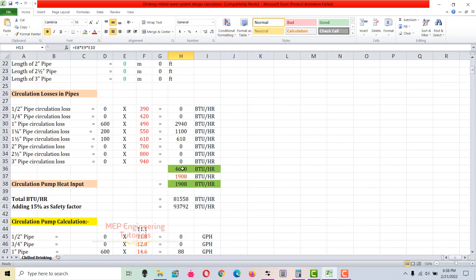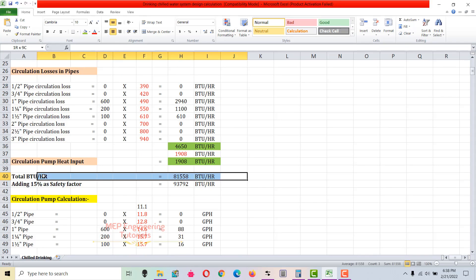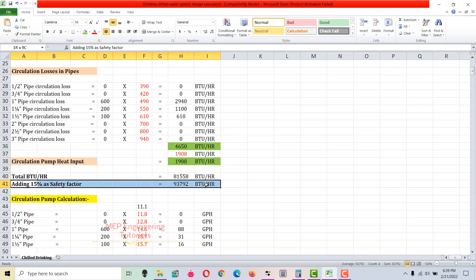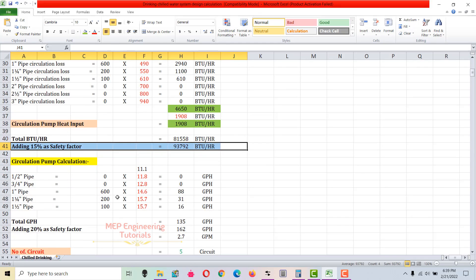Now we add all the loads: 75,000 + 4,650 + 1,908, giving a total of 81,558 BTUs per hour. We then apply a 15% safety factor, so the total BTUs per hour is 93,792 BTUs per hour.